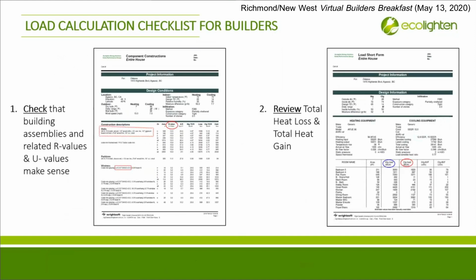Load calculations are owed to you. You own them. So this should create the expectation that they are going to be done and going to be done properly. And they are going to be delivered to you for your review. There's a lot of pages of numbers, but all you need to know are a few things to review. First of all, check to make sure the area of the house you're building and the area of the house on the calculation results don't vary more than 3 or 4%. If it's more than that, it usually means there's an error input somewhere.